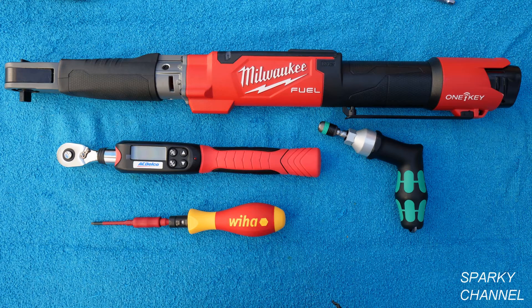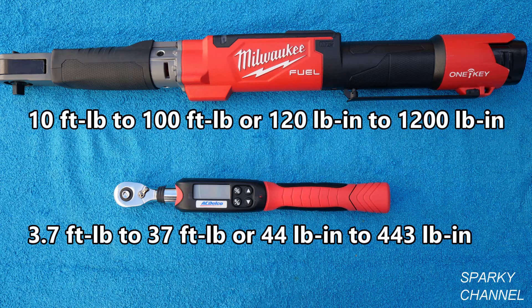Below that is the Wiha torque screwdriver that is 1000-volt insulated. Looking at the two torque wrenches: the Milwaukee has a torque rating of 10 to 100 foot-pounds. To convert to pound-inches, you multiply by 12, so that's 120 to 1200 pound-inches. The AC Delco is rated 3.7 to 37 foot-pounds, which is equivalent to 44 to 443 pound-inches.